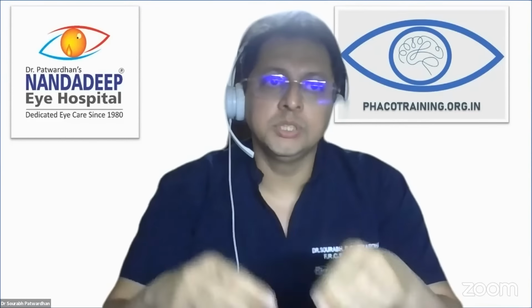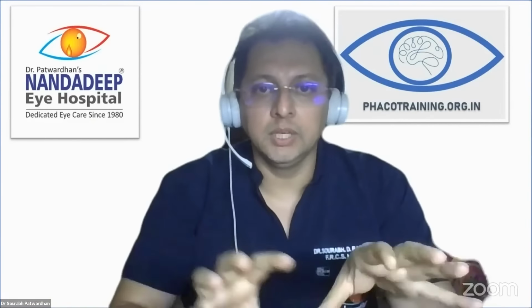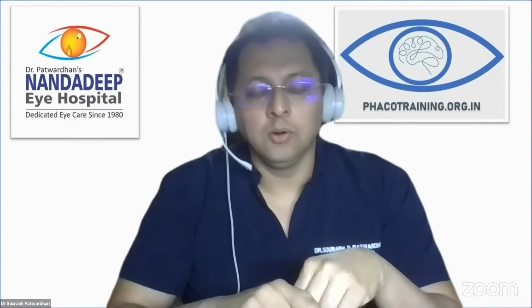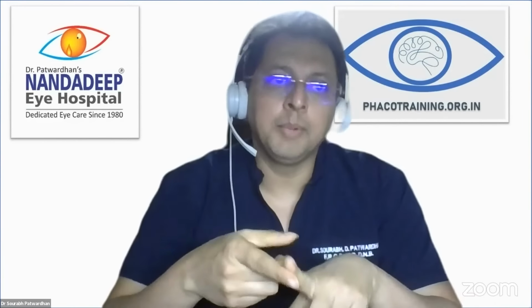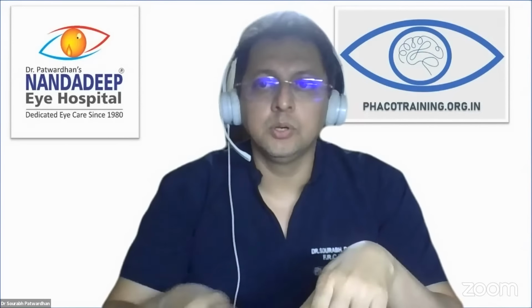Okay. In addition, we do biological indicators. Yeah. Biological indicators are absolutely useful for making sure that whatever machine you are using is actually working. But the problem is that we cannot use it immediately because it takes 24-48 hours. So it's for continuous monitoring of the working of that equipment. And apart from that, the BD test is very important. I think many people don't do that for autoclave. Bowie-Dick. So every day, the first cycle you should run with the Bowie-Dick. That means on that day, the vacuum is being properly done.